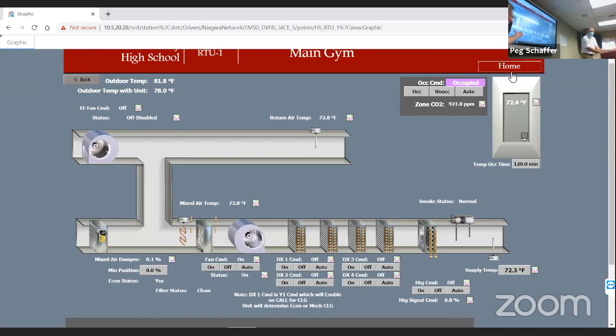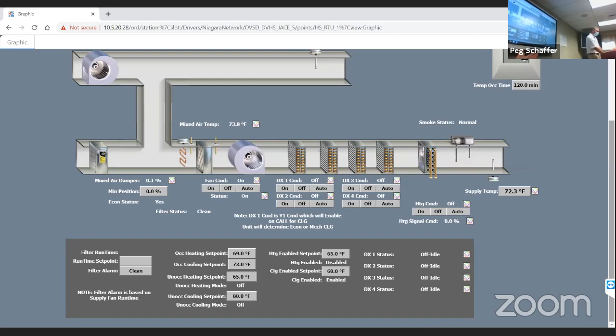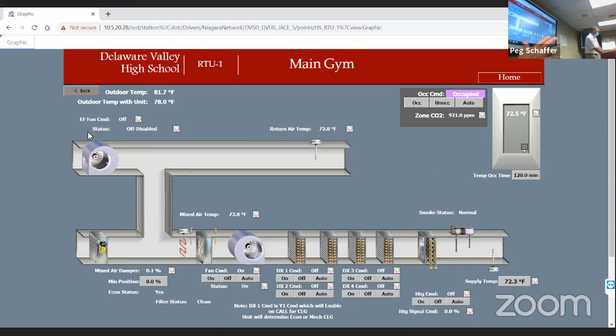It's telling you the fan is commanded on and it is running. You could see the fan is running. It tells you what the discharge air temperature is; the supply air temp of that unit is 72.3 degrees Fahrenheit. Through the service contract that we have with the school district, we calibrate those devices regularly so that we know that information is accurate. If we find that it is not accurate as we're doing our preventative maintenance, we'll look at it, figure out what might be wrong with it, and bring those details to Marvin's attention so that your staff can take a look at it and we can assist with helping.